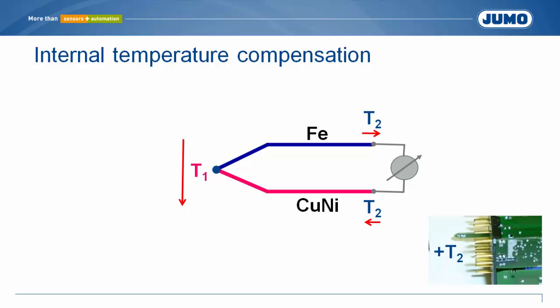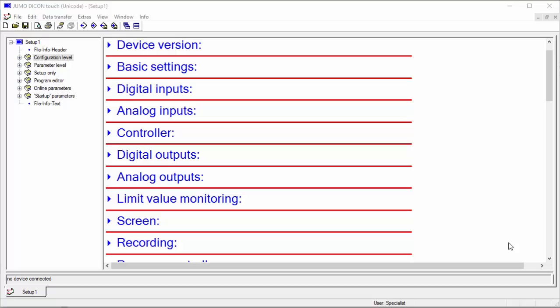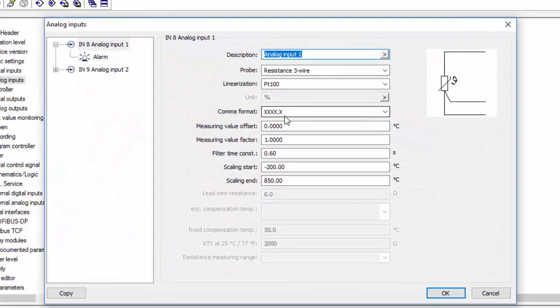Regarding thermocouples, the terminal connection is called the reference junction. Correspondingly, the temperature at this point is the reference junction temperature. For JUMO field devices, so-called setup programs are available. These programs are used to configure the devices. For the respective input, probe type thermocouple with internal temperature compensation must be selected.